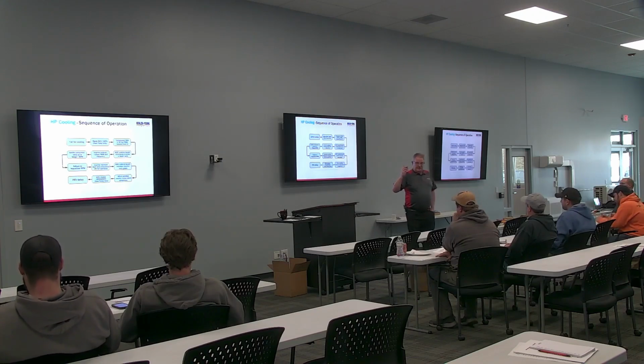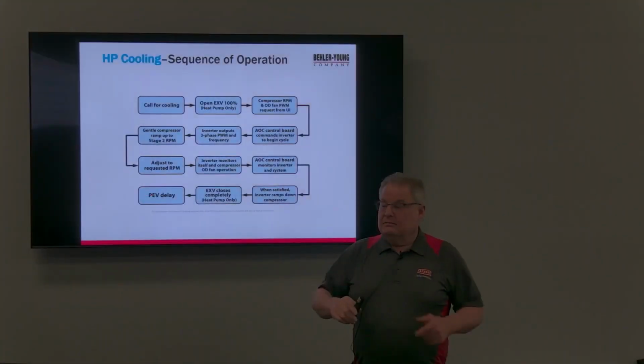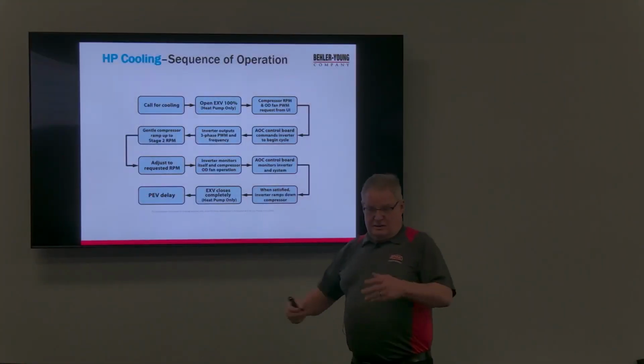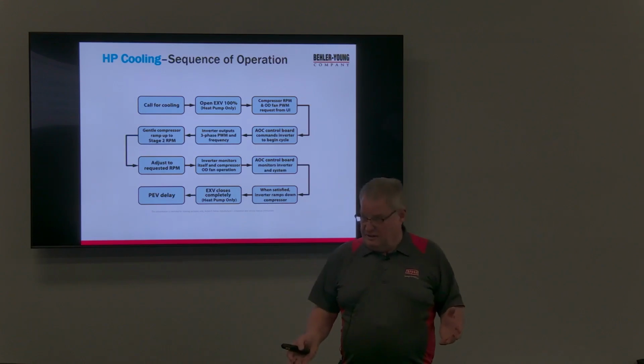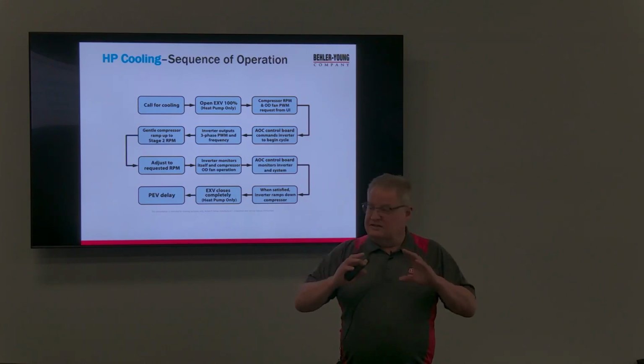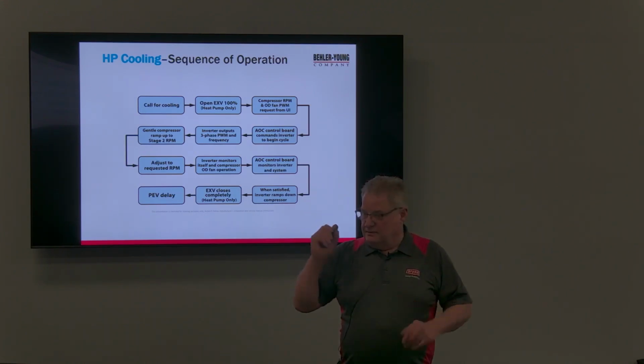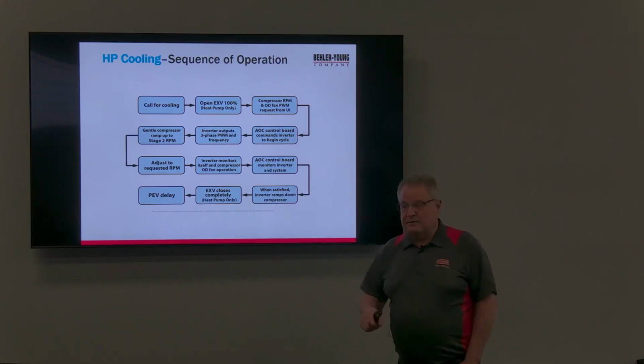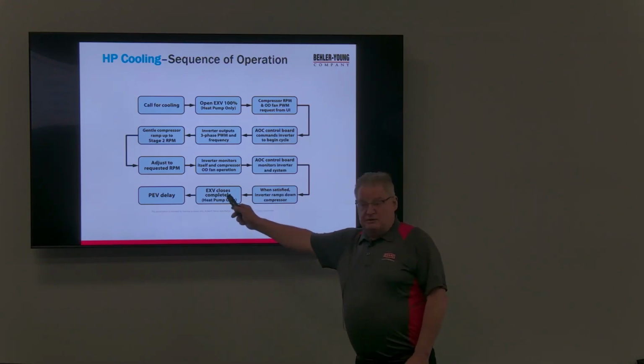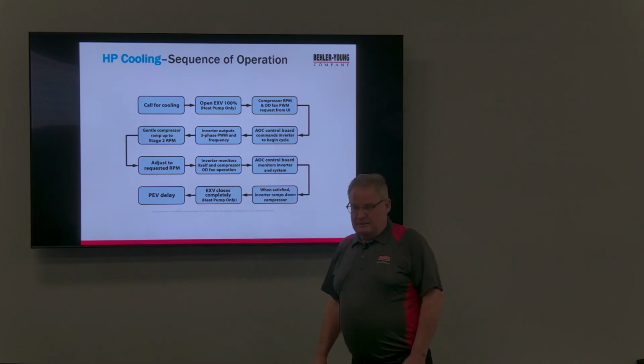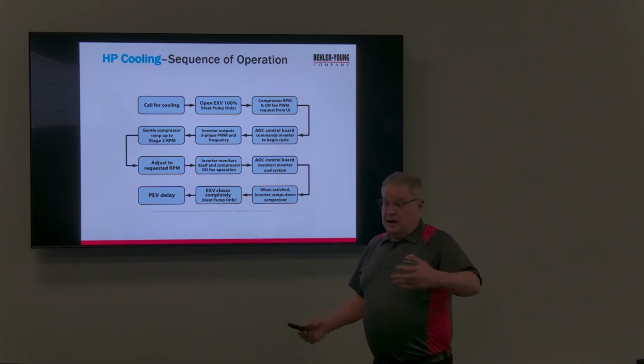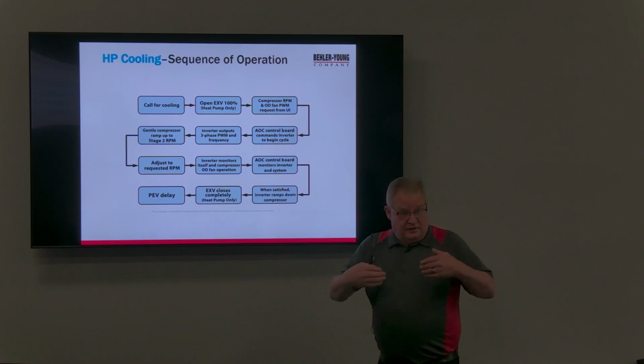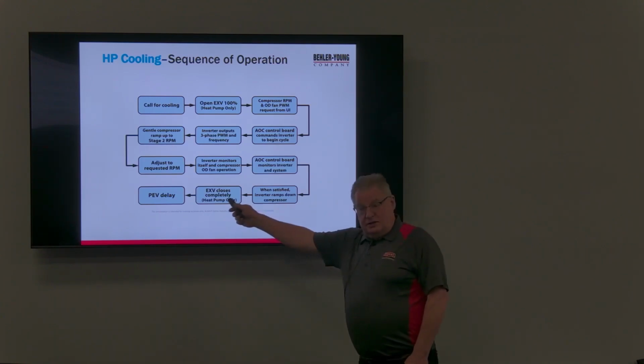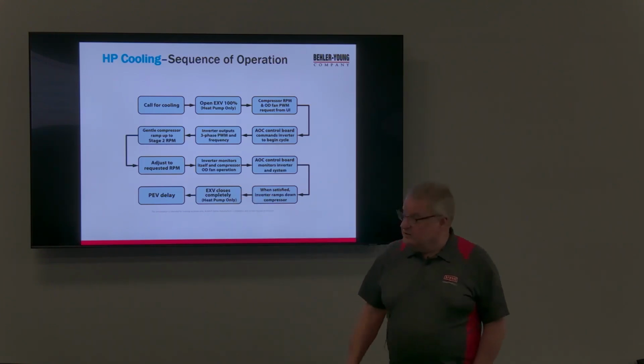Now, what's this going to mean during evacuation? We have to open that valve. Okay, so we've got to know that this is what it does because, you come to this unit, it's cooling, you need to pull the charge out of the thing, right? You've got to go into the control and you have to drive the valve open. Okay, there's a service mode there to drive it open. So we've got to remember if we're dealing with a variable speed, we've got to drive that valve open. Okay, because that's at that liquid line. Brand new, it doesn't matter, right? Because the unit's pre-charged, we're not getting into it. So if we don't, again, we're not going to get a proper evacuation.